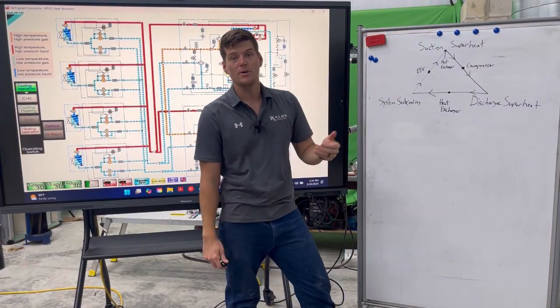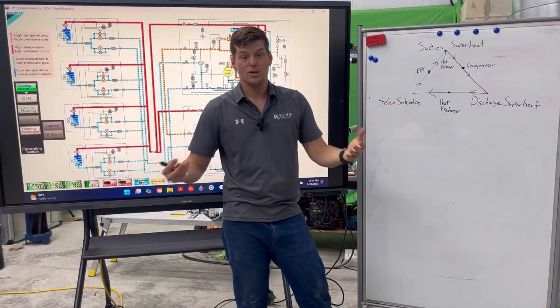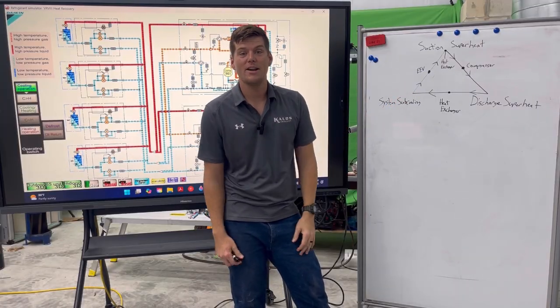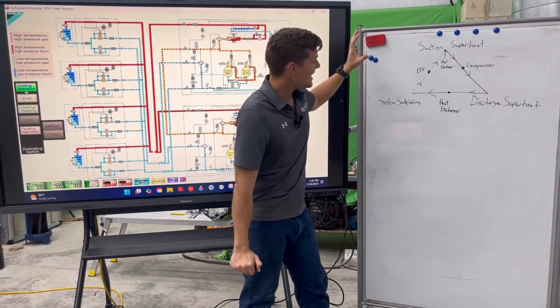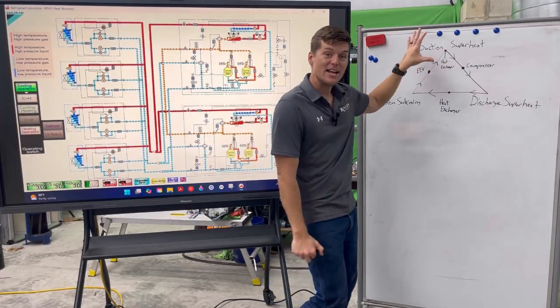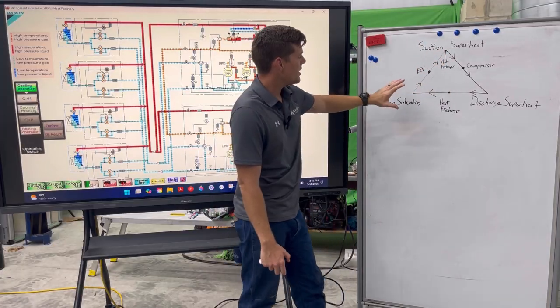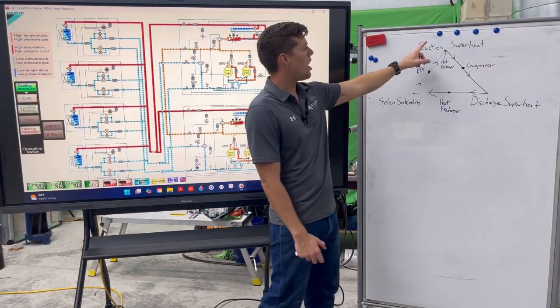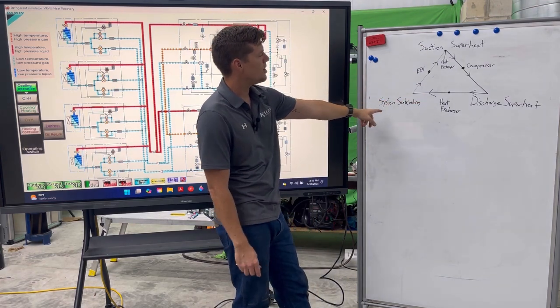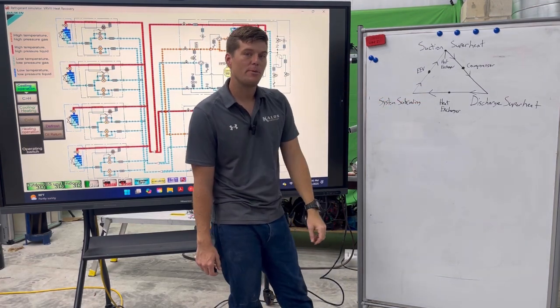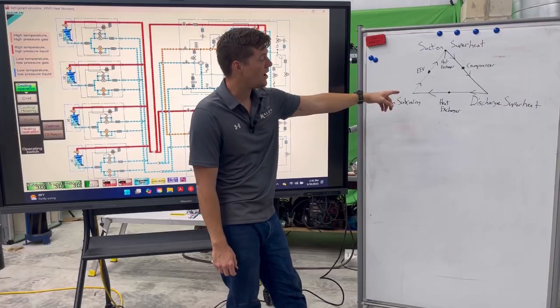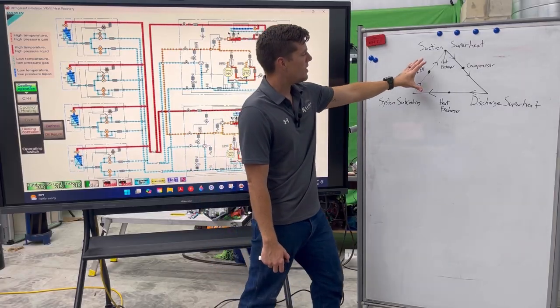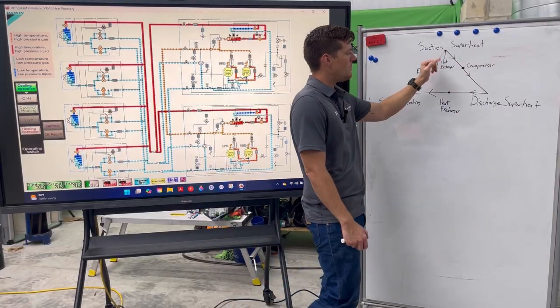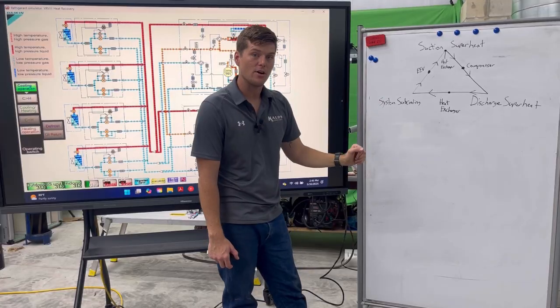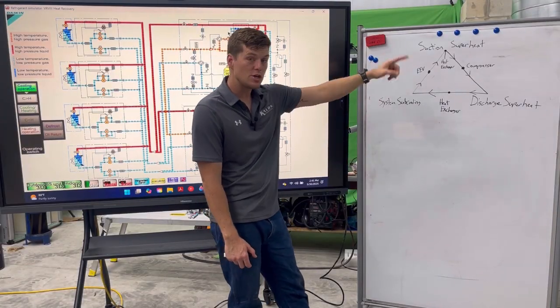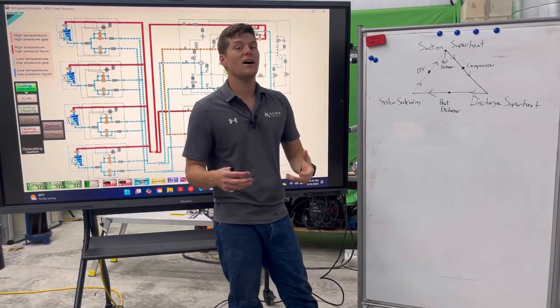Now, I drew you a triangle because a triangle is nature's strongest shape that we find out in the real world. And here, we use this as our troubleshooting tree. Now, you can get rid of all the other stuff in between and just plot suction superheat, discharge superheat, and system subcooling. But the reason I added all the components on this troubleshooting triangle is because this allows us to fill in the information that we may have connecting these 3 together. Remember, you need these 3 numbers in these 3 corners to form a solid diagnosis.